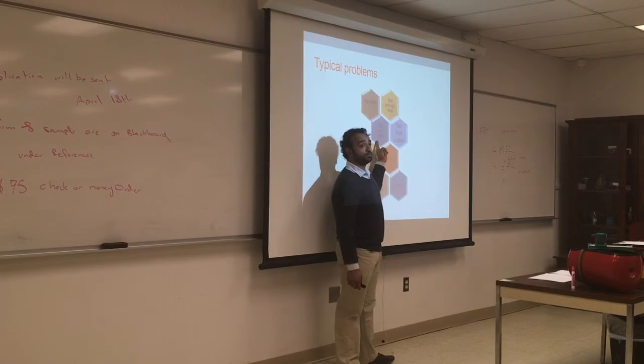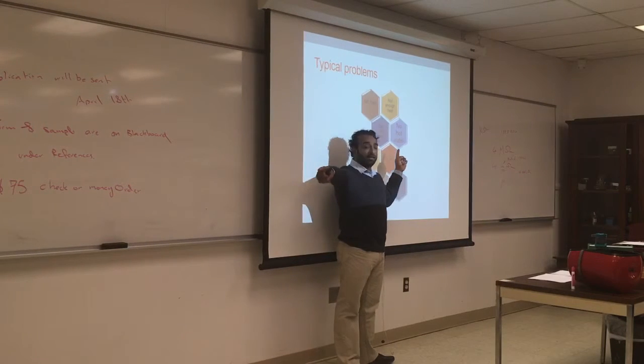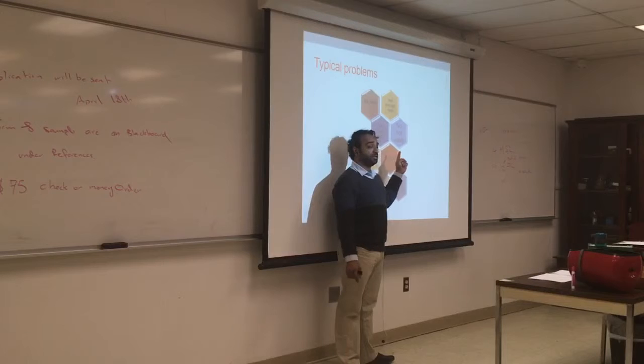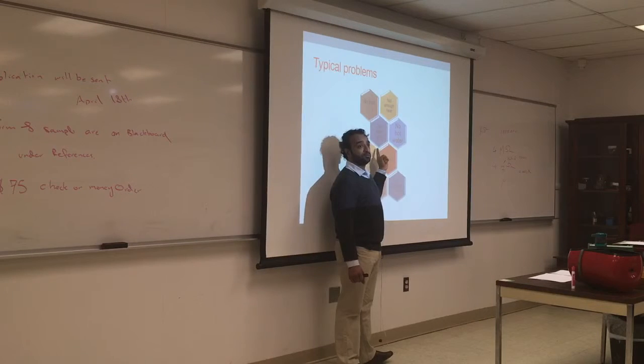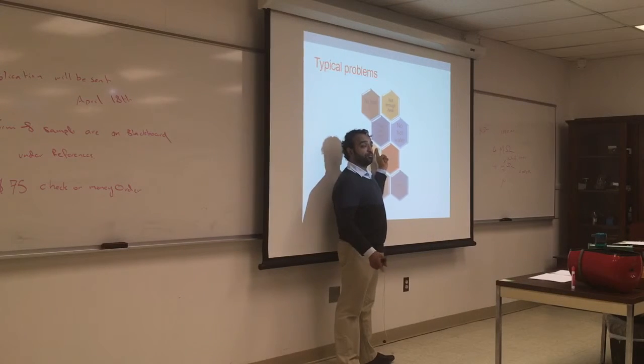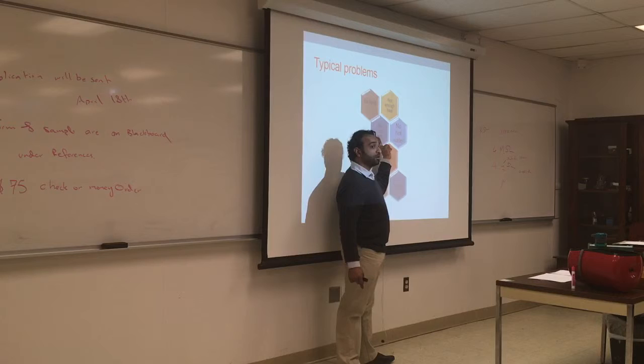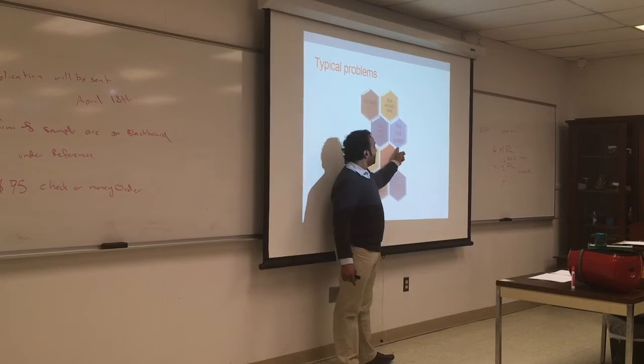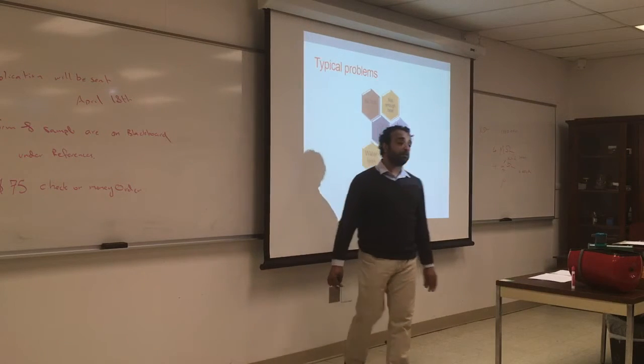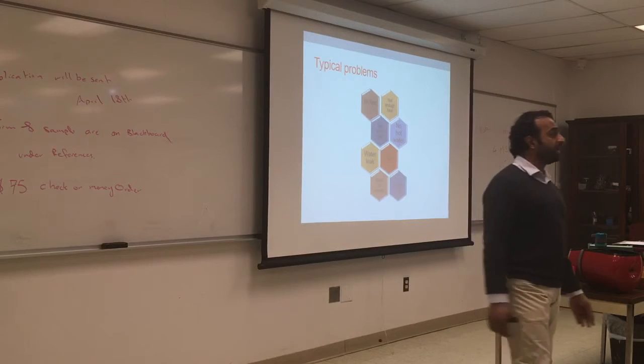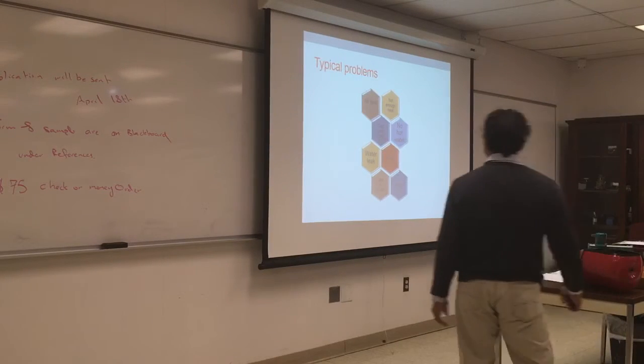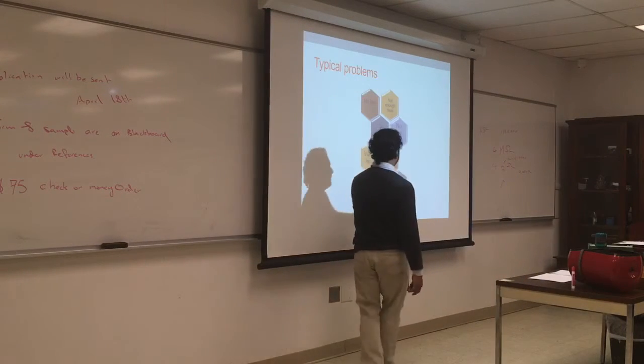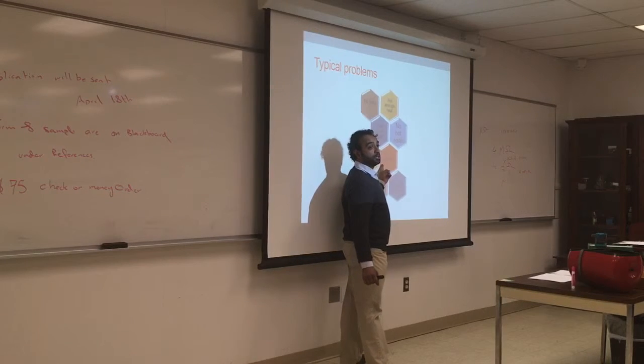Too much water flow. Again, in the other class we talked about the radiator and how it's designed at 180. What if you run the water at 200 or 220? You're probably going to have too much heat. Something is faulty in the setting of the system, so you've got to go and check all the settings and all the numbers. No hot water, assuming we have an auxiliary hot water tank and water goes through it, so that's another issue.